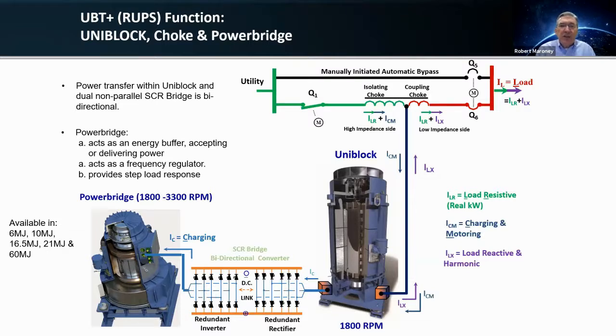You'll also notice we're using an SCR bidirectional converter bridge between the energy storage device and the uniblock. And we use this because the flywheel, like the batteries, operates at a different voltage than you're using on frequency. So our flywheels run about 785 volts AC, 1,000 hertz at full speed. You'll also notice that I comment here that the power bridge can run anywhere from 1,800 to 3,300 RPM. One of the benefits of a rotary UPS like this is we can do something that the static traditional guys have a hard time with.